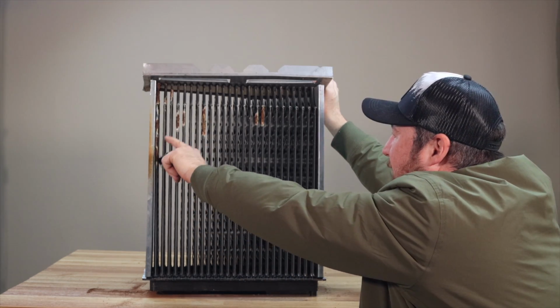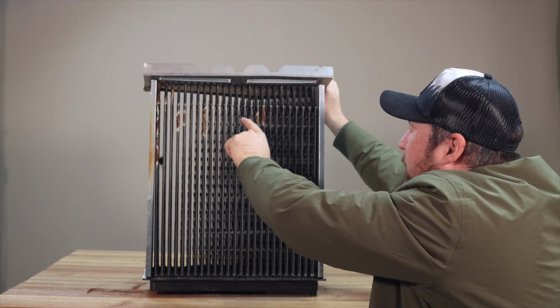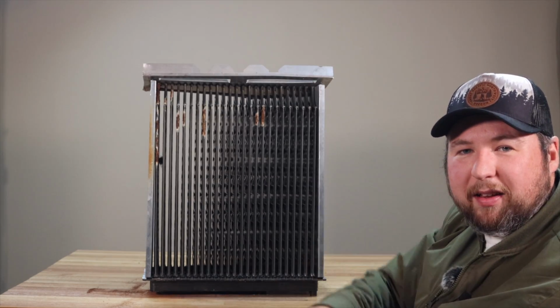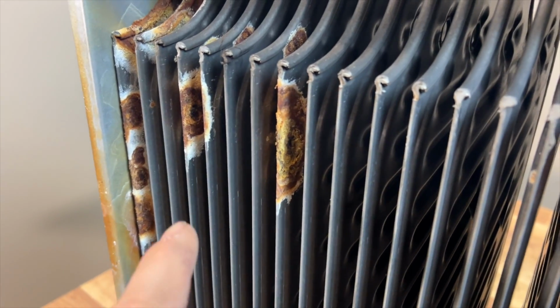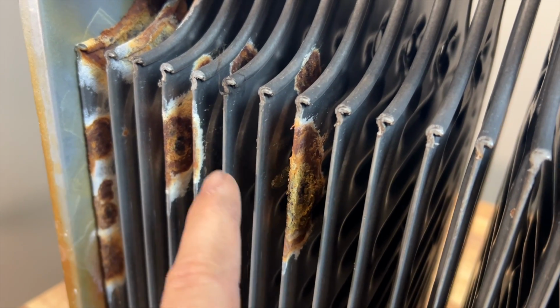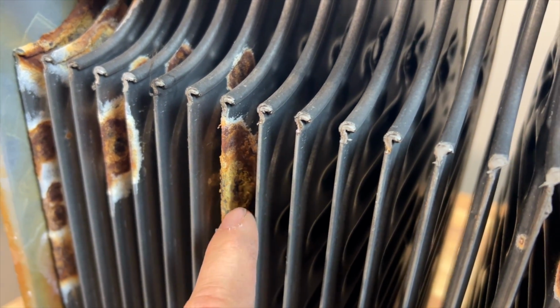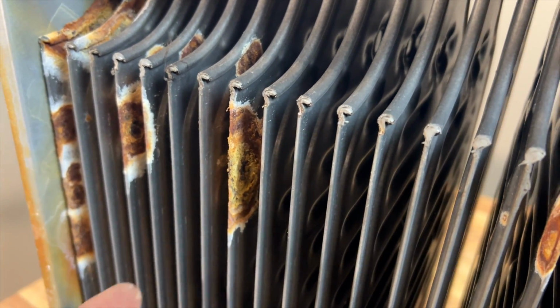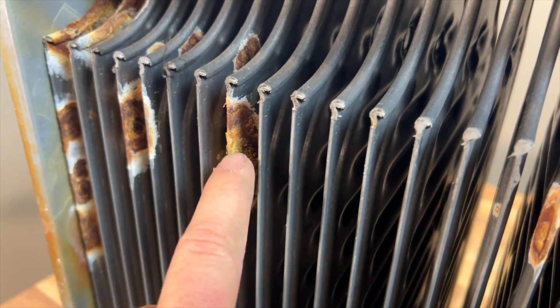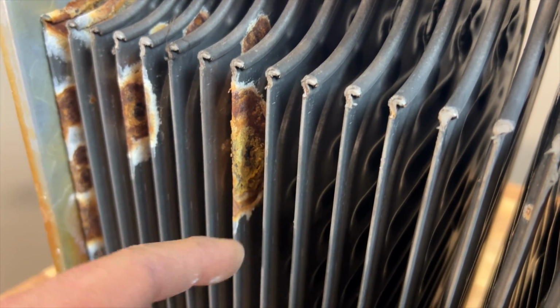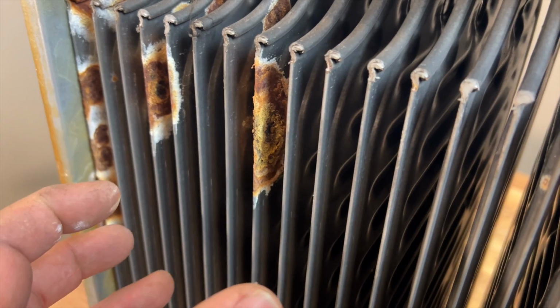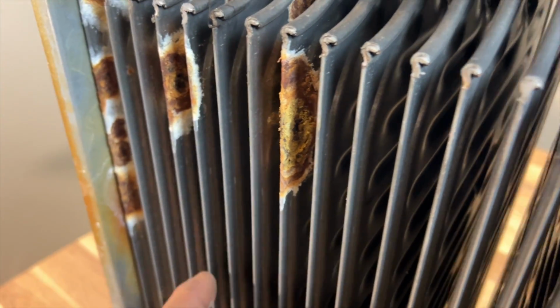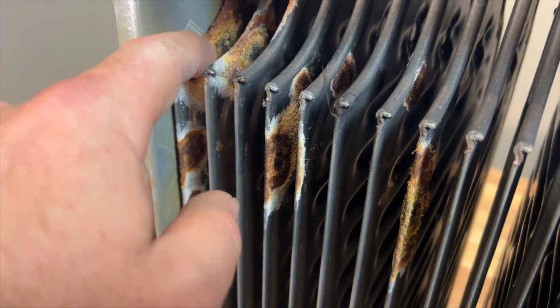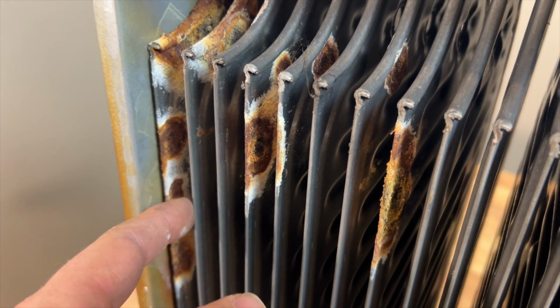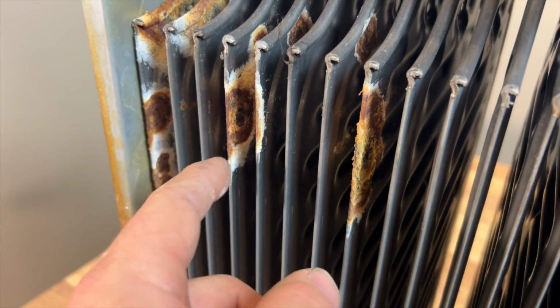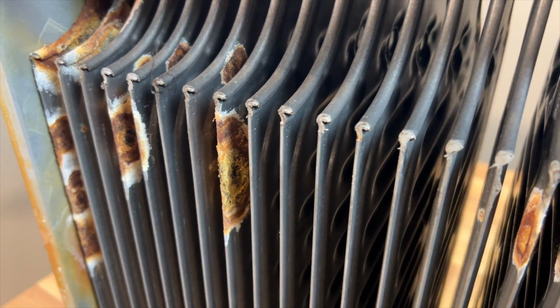As you can see here, there's quite a bit of rusted out points. Let's get a close-up of that. So as you see here, you can see that it's rotted out. And this is because you had improper combustion, which produced a lot of nasty stuff, acidic stuff, and it sits in the water because, like I said, these things don't drain 100%. And so what ends up happening is it starts to eat away from the inside out. So this is obviously a compromised heat exchanger.